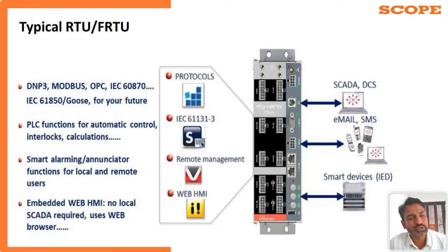But normally, when you are purchasing the RTU, you have to keep in mind the web-enabled HMI. This is important when you want to locally monitor the system, where you install one RTU at the substation. By connecting your laptop to that local RTU, you can see the single line diagram. For that, you need the web HMI built in, so that you can see the single line diagram, the alarms, the events, and even the graphical representation within the RTU.